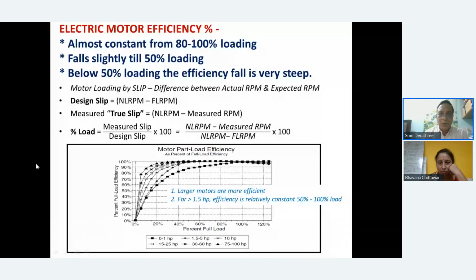If you see the efficiency curves in the motor, especially on the higher kilowatt motors, efficiencies are almost close to the rated efficiency, almost 90% plus in this range. But the lower kilowatt motors, these are the bottom ones, you see their efficiency fall is very steep. Here it is almost constant, but they start falling very steeply. These are motors up to, I would suggest, maybe around 18 kilowatts.